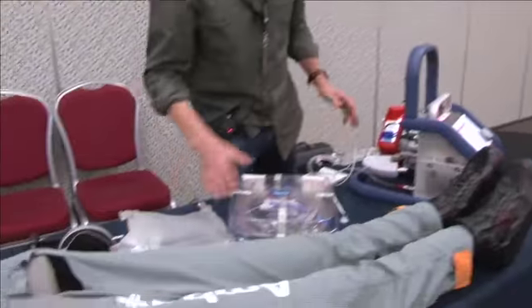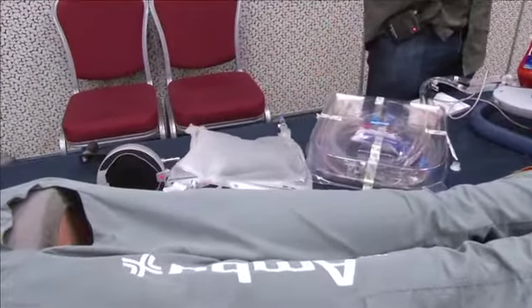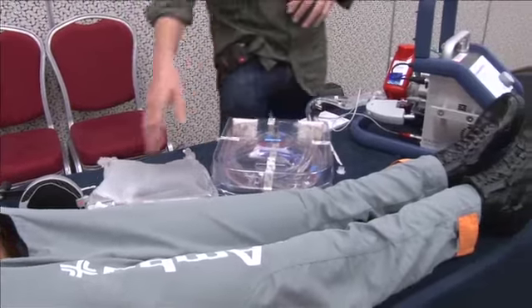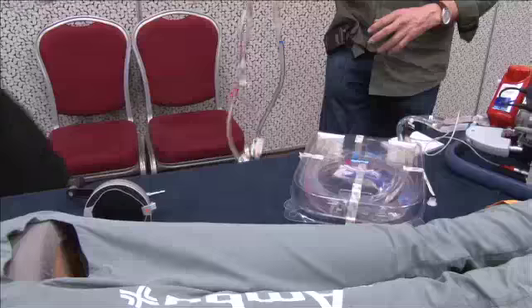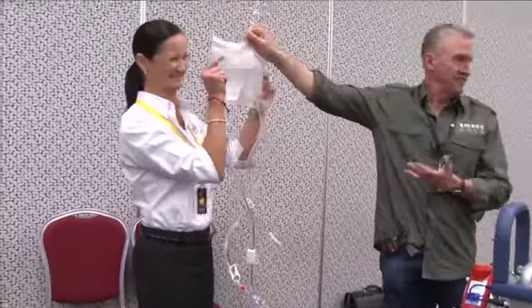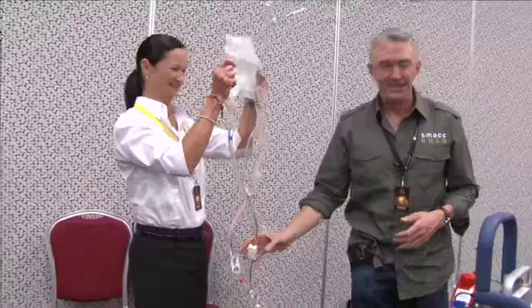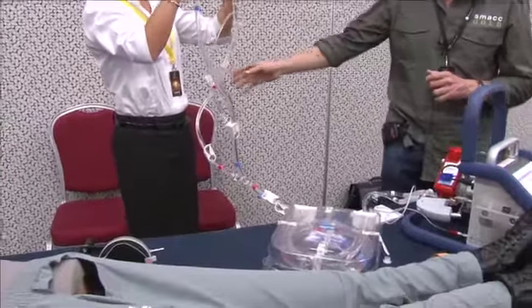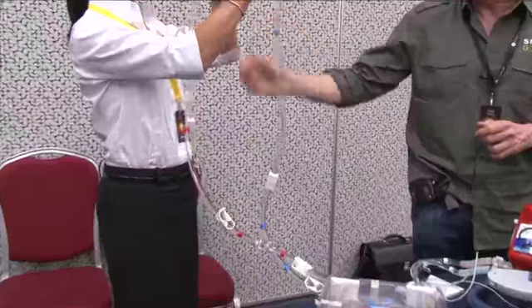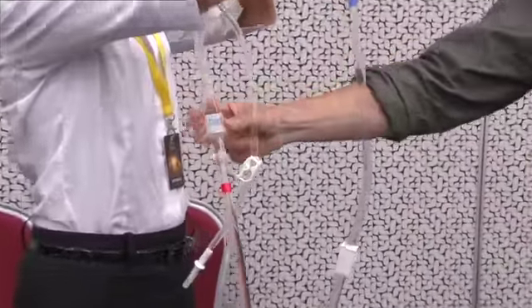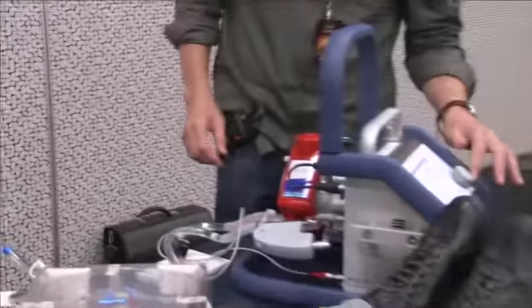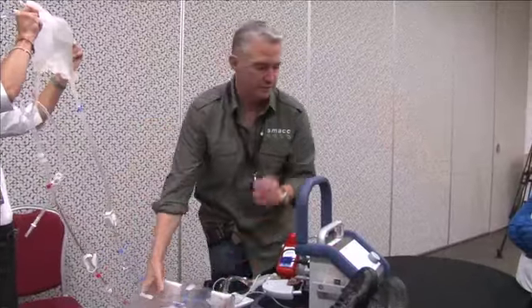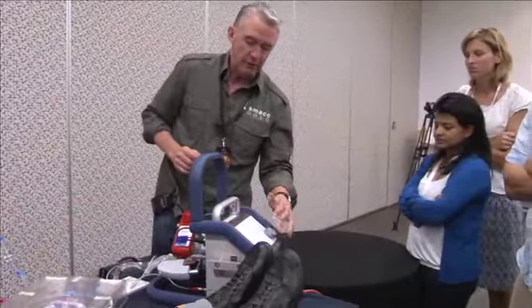So once the circuit's all set up, you've got your pressure zeroed. The next thing you want to do is prime the circuit. Here's my IV pole. So this is actually very, very straightforward because this circuit comes with some one-way valves. There's a little duckbill valve here that's one way. And so all we do is start the pump running. We've now re-established flow. And now we've got flow around the circuit.